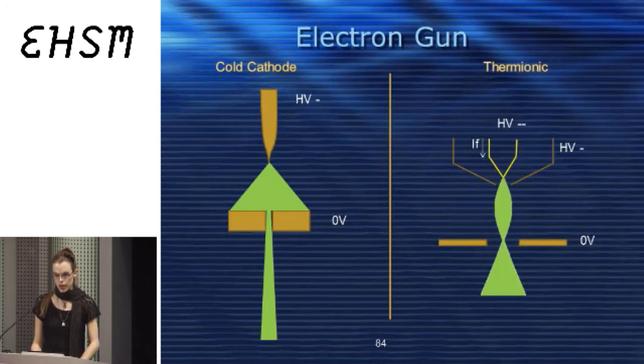Two types of electron guns that we've been working with are the cold cathode electron gun, which works at about 5 to 50 to 100 millitorr, depending on the geometry. And I like that because you don't have to use the turbomolecular pump. You don't have to get to 10 to the minus 6 to make this work. Thermionic, on the other hand, you have to heat the tungsten filament over here up to several thousand degrees. It starts emitting electrons. And then you use this structure called the Wehnelt to only allow emission off of the tip, and you get this beam.